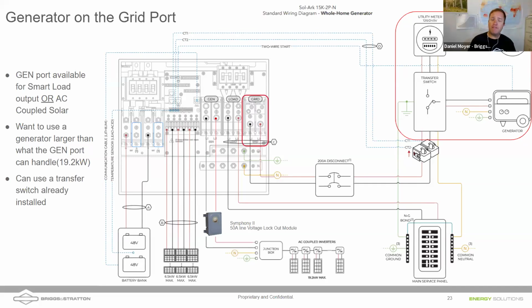One quick thing, last comment on those Symphony 2, those also can be used as load control if you're just doing a generator. So they can be programmed to curtail loads in priorities when the generator reaches a certain load point. Lastly, we're not showing it here, but you do need to run a neutral to that Symphony 2 line module because the contactor in there is using 120 to operate that contactor as well.